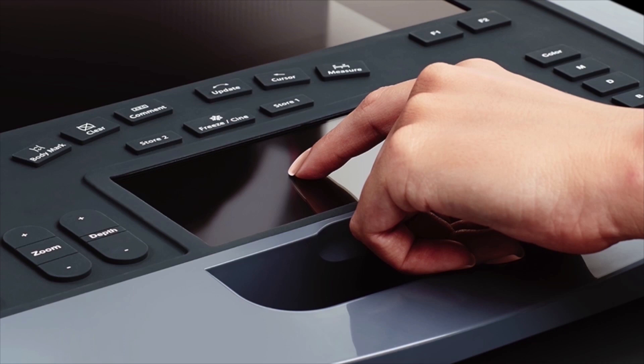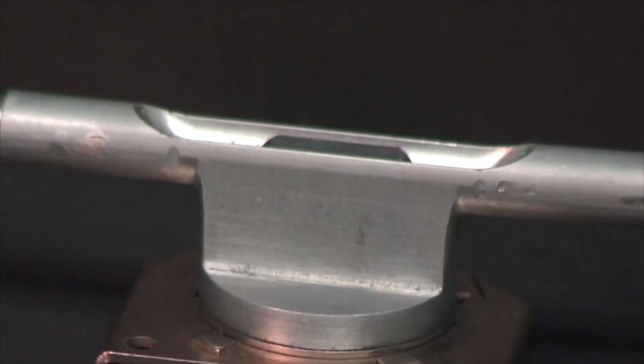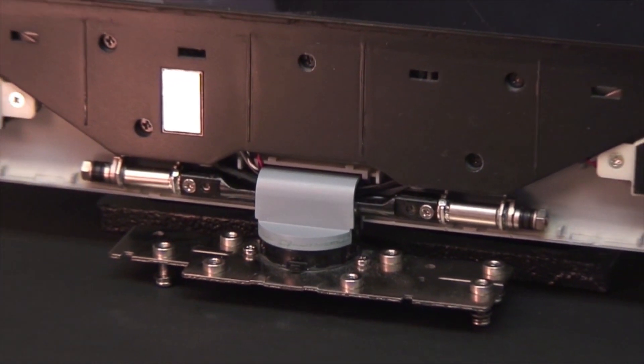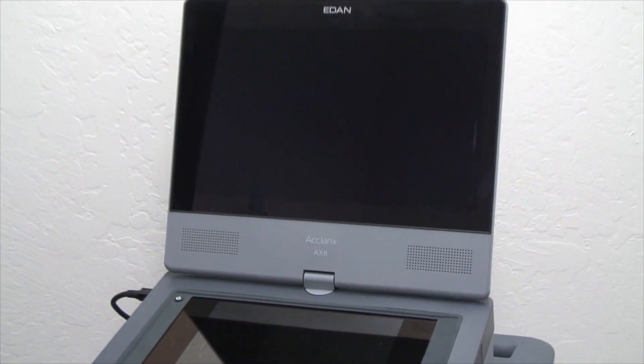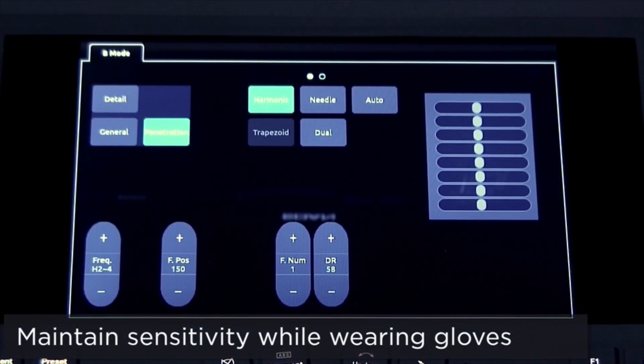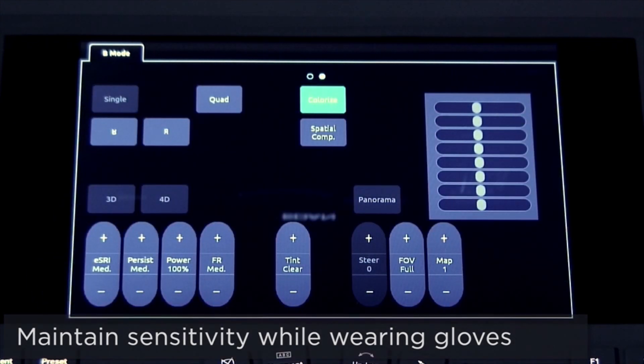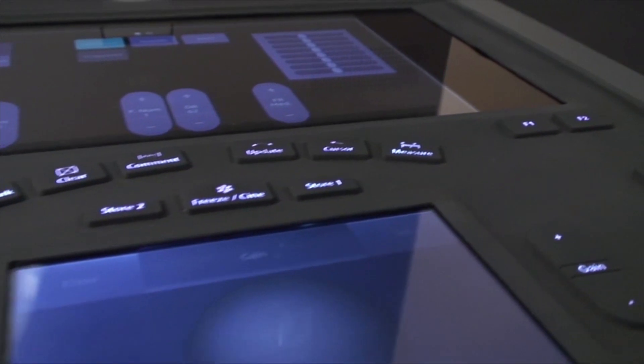Using the highest quality materials provides not only the exceptional fit and finish you see, but adds functionality and durability to the system. The 15-inch monitor is a very high-quality, high-definition monitor for exceptional grayscale contrast and color display. The hinge on the monitor was specifically engineered for the system and cycle-tested through tens of thousands of activations, ensuring durability. The touchscreens were specifically selected because of their ability to maintain sensitivity even while wearing gloves. The control panel is encased in a durable siliconized rubber, which wears well for easy cleaning and adds a layer of protection.